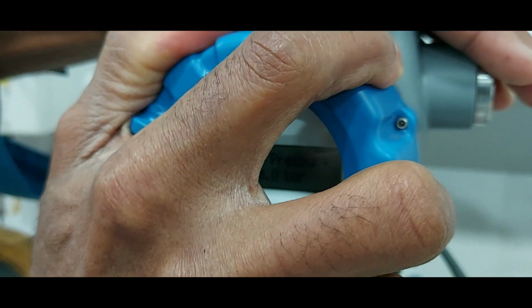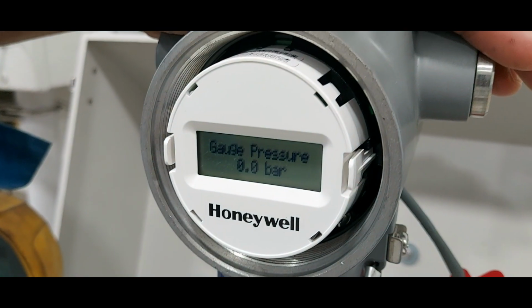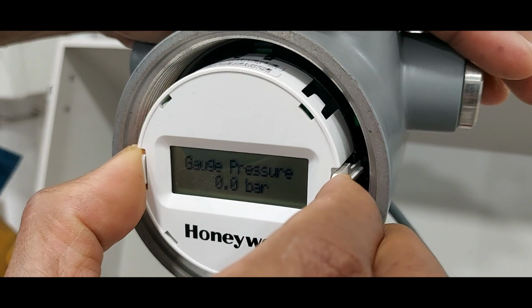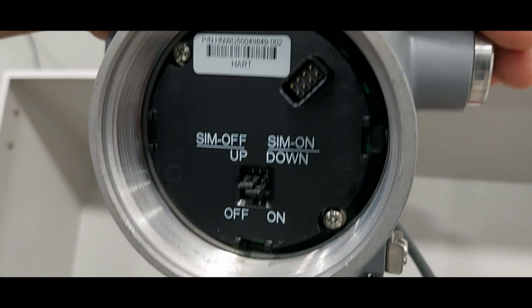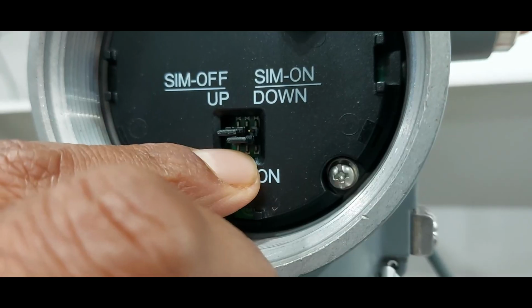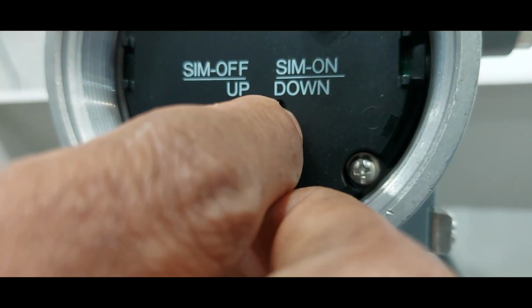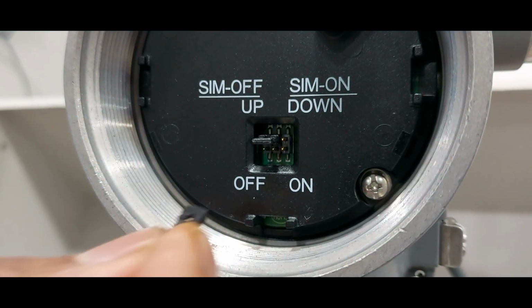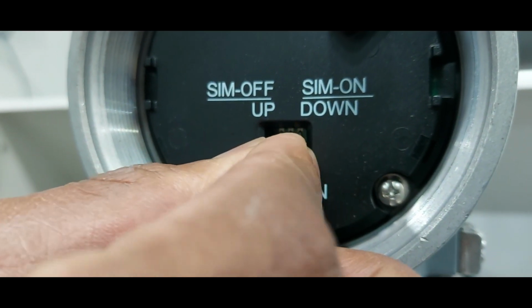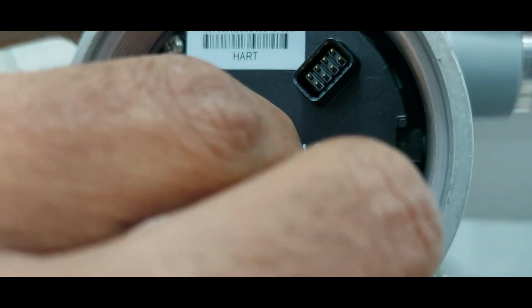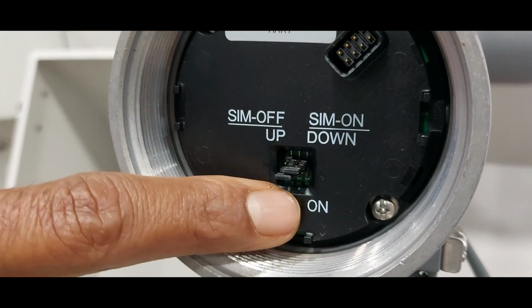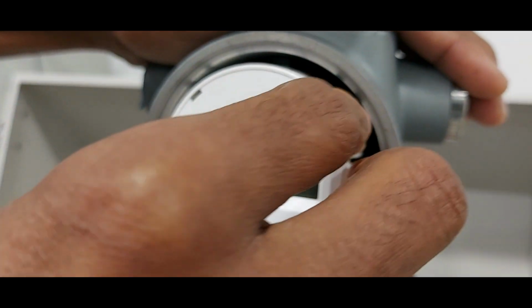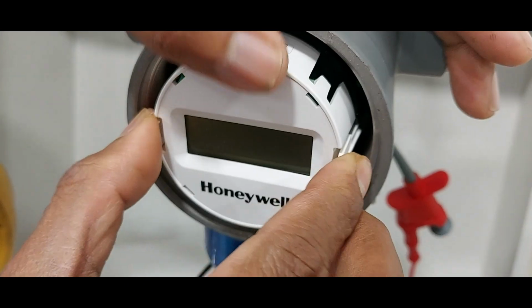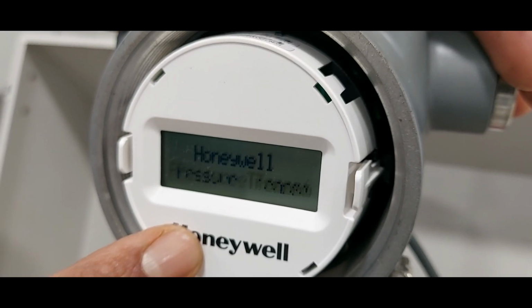Open the front cover. Remove the display from the unit. This is security option. This is simulation mode. First we remove the jumper from the downside. On. Put it to off condition. We also enable the simulation mode. Now simulation mode is enabled. Security mode is off condition. Return back, connected to the display. Now display is connected.